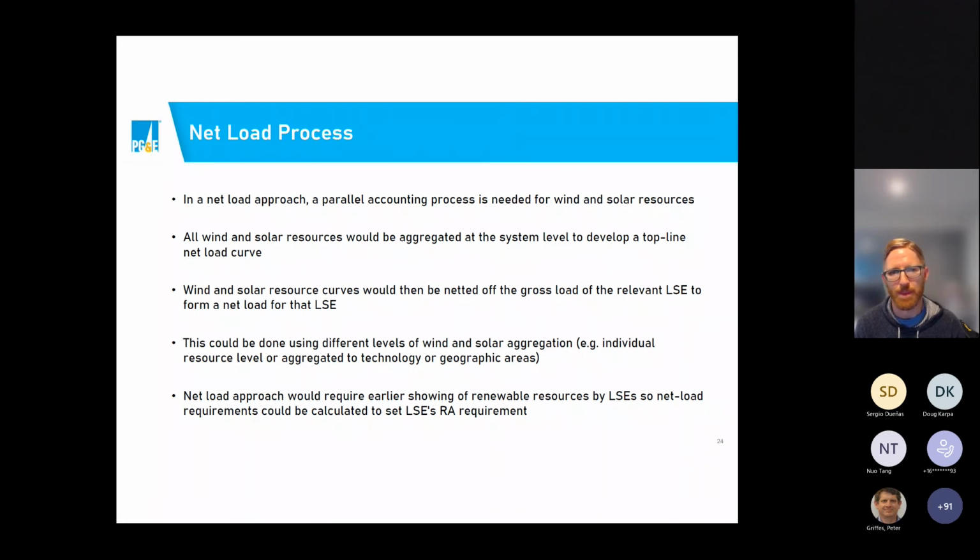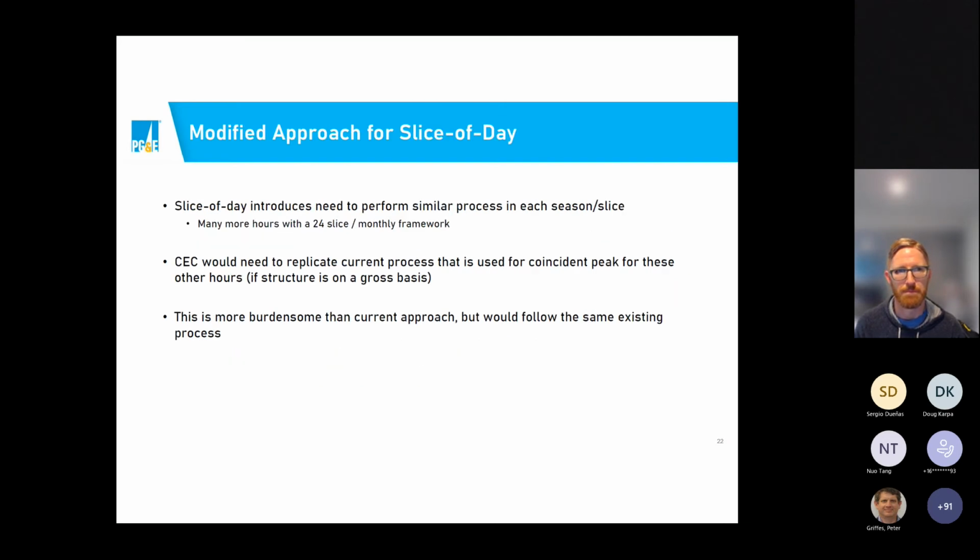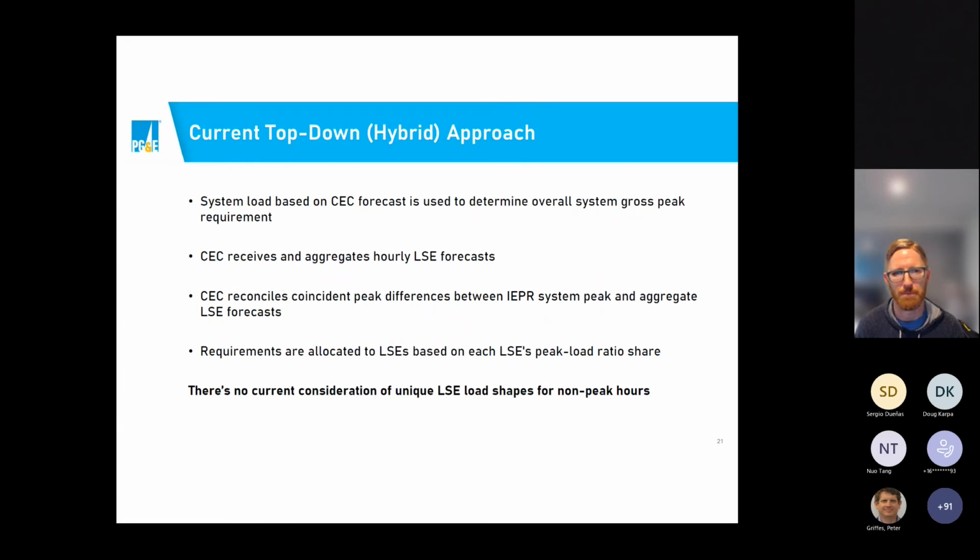It seems to me you're glossing over the process the CEC undertakes, which factors into the RA requirements. First of all, each load serving entity provides their hourly historical loads to the Energy Commission, and they provide a forecast. The Energy Commission takes each LSE's submittal and does both a plausibility check and a coincident adjustment.